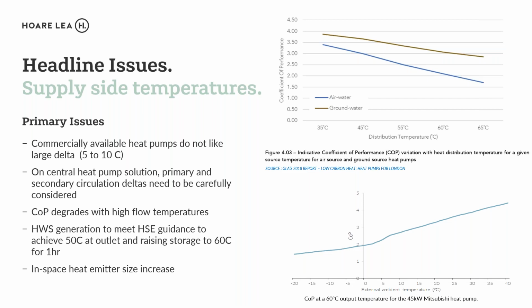And heat pumps do not like a very large delta T across them. So the primary, if you do primary circulation, is on a high volume flow rate. And obviously to get pipe sizes down, you need to look at your secondary distribution, whether you actually do that on a higher delta, which is normally the case. So you do end up with a high primary flow rate and a decoupling of secondary. So then you need to take that into consideration. And obviously you do have COP deficiencies when you start going up in temperature, but also at very low ambient temperatures, where you actually need the heat most, the COPs downgrade. So you do lose the benefit of the heat pump on air source, that is.